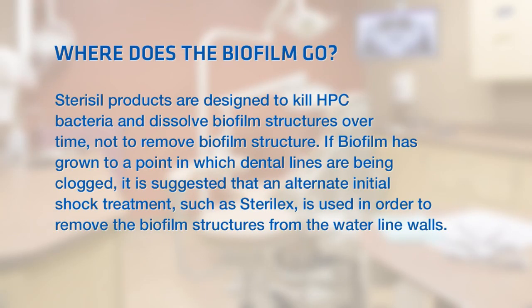Where does the biofilm go? Sterisil products are designed to kill HPC bacteria and dissolve biofilm structures over time, not to remove biofilm structure. If biofilm has grown to a point where dental lines are being clogged, it is suggested that an alternate initial shock treatment, such as Sterilex, is used in order to remove the biofilm structures from the waterline walls.